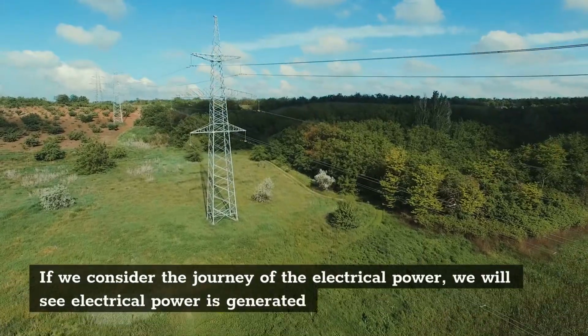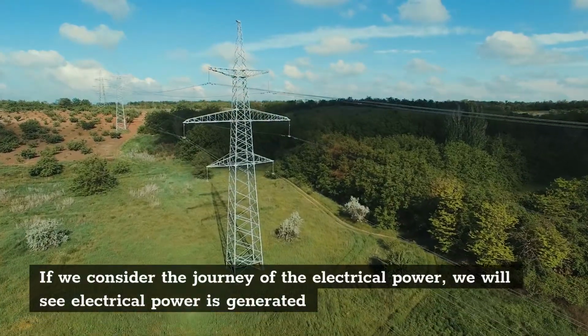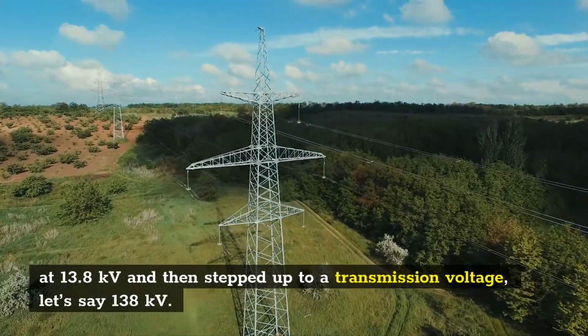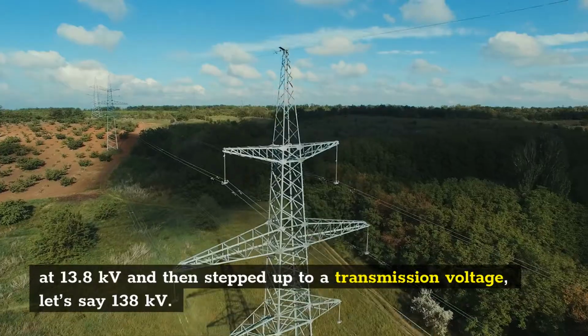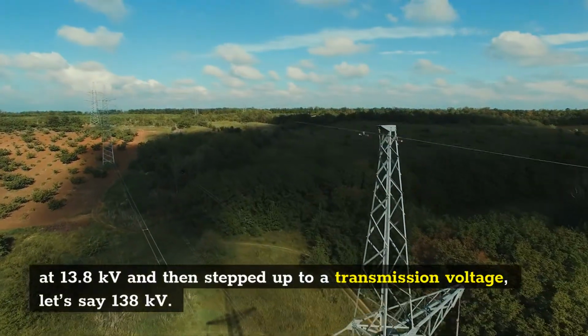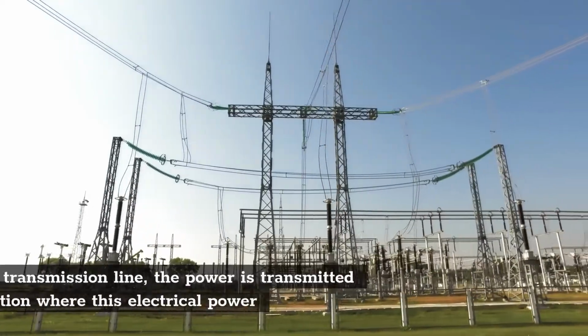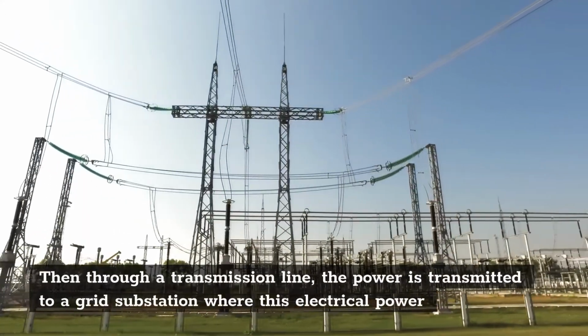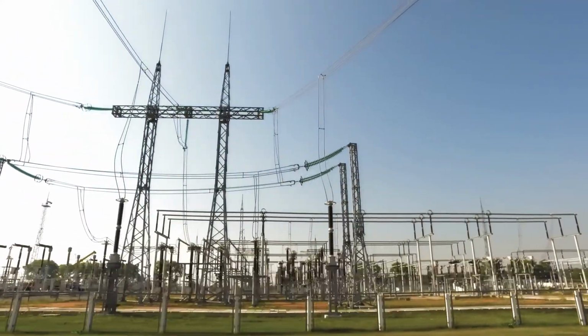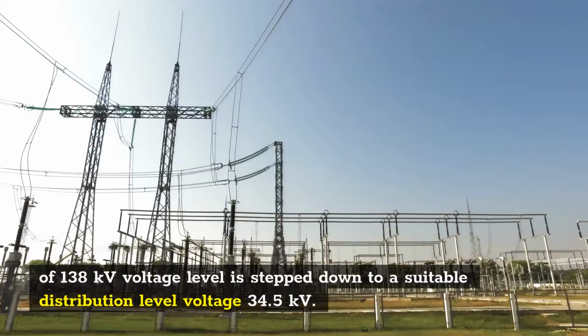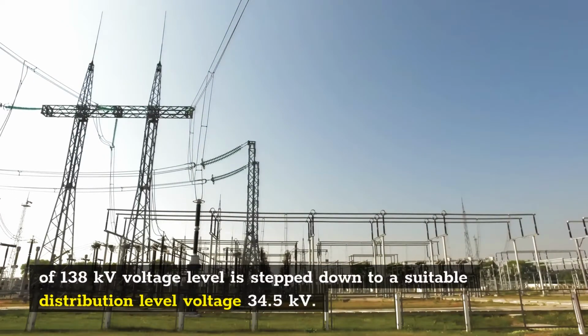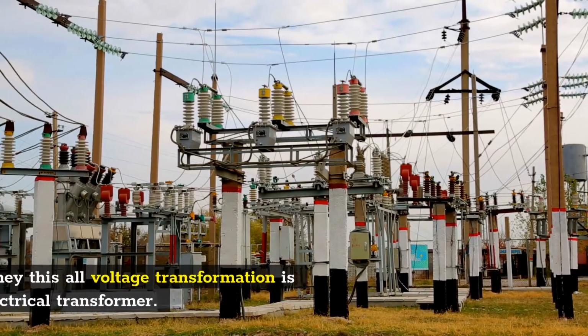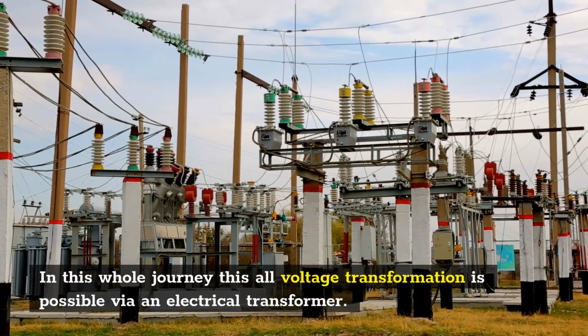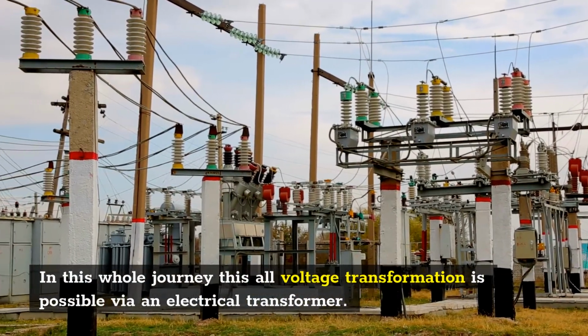If we consider the journey of the electrical power, we will see electrical power is generated at 13.8 kV and then stepped up to a transmission voltage, let's say 138 kV. Then through a transmission line, the power is transmitted to a grid substation where this electrical power of 138 kV voltage level is stepped down to a suitable distribution level voltage, 34.5 kV. In this whole journey, all this voltage transformation is possible via an electrical transformer.